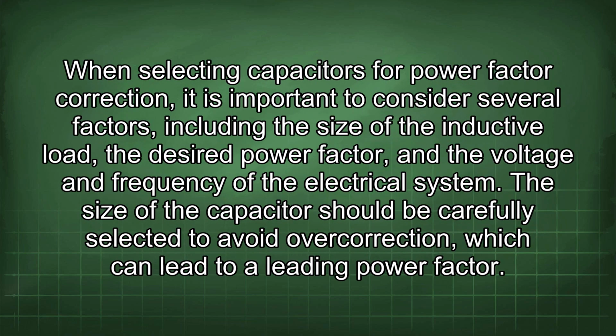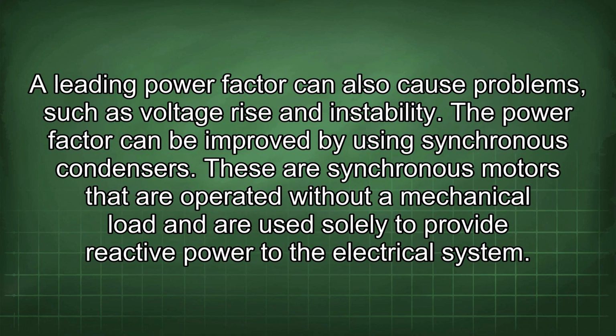When selecting capacitors for power factor correction, it is important to consider several factors, including the size of the inductive load, the desired power factor, and the voltage and frequency of the electrical system. The size of the capacitor should be carefully selected to avoid overcorrection, which can lead to a leading power factor. A leading power factor can also cause problems such as voltage rise and instability.